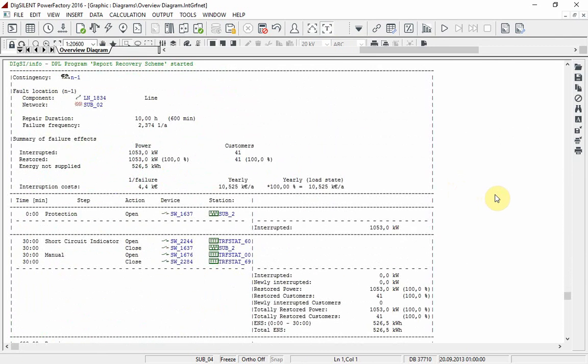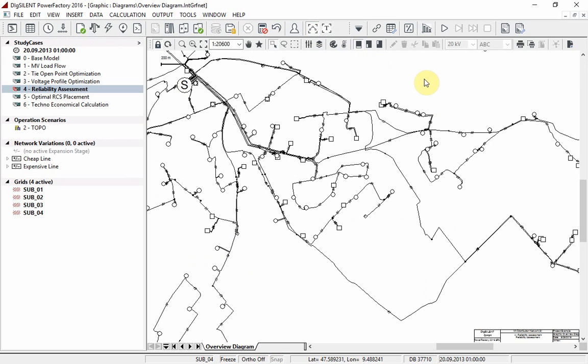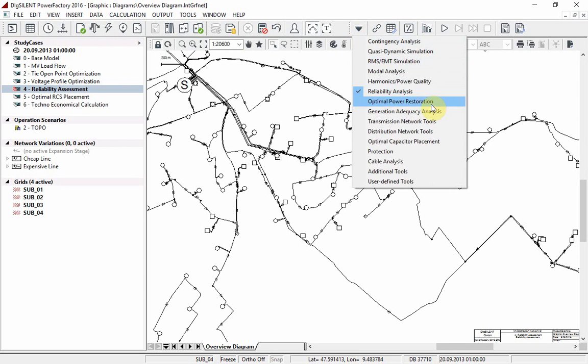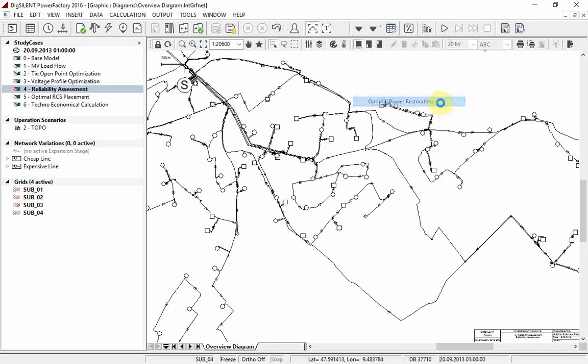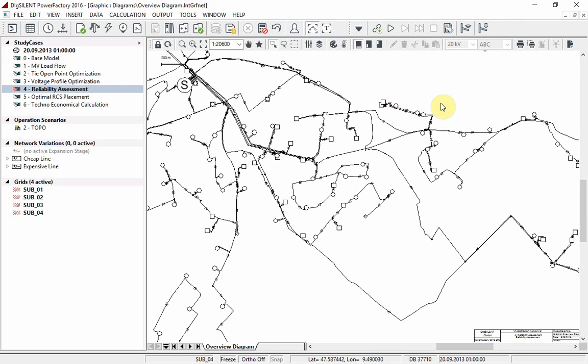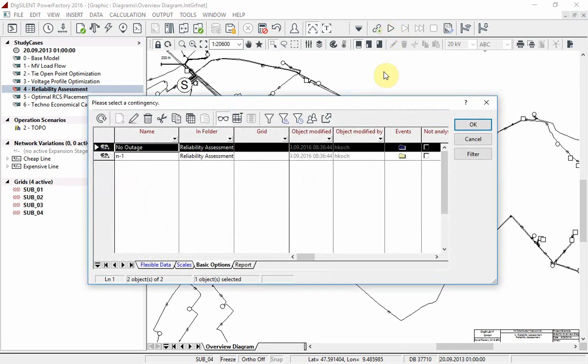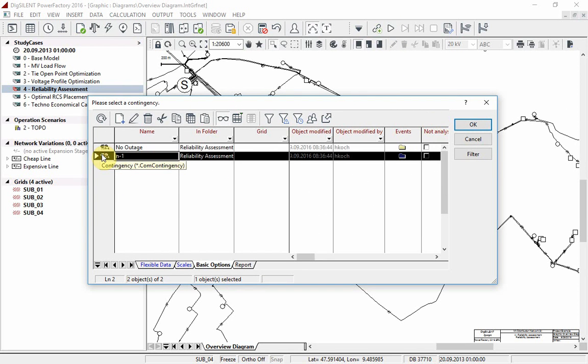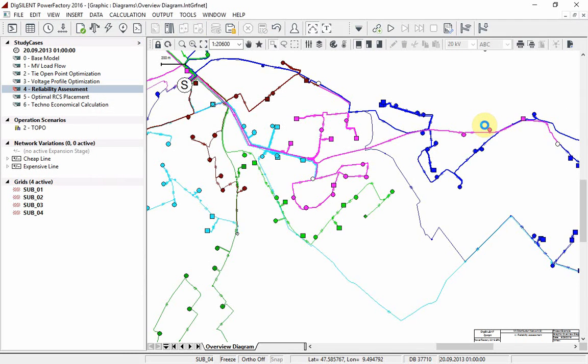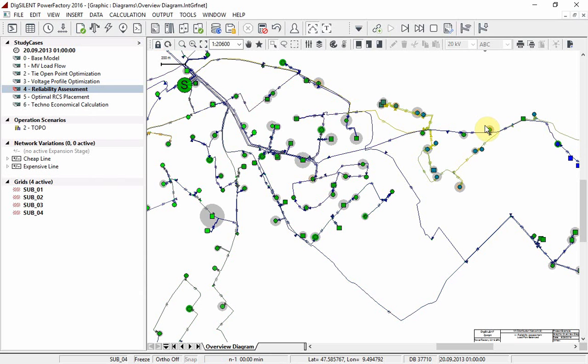Here you can see the calculated steps to achieve optimal power restoration. Returning to the single line diagram, change the toolbox to optimal power restoration. You can see a step by step trace of the events associated with the optimal power restoration. Select the option start trace. Choose the contingency n-1, select OK. First the load flow is calculated. Move to the next step of the trace.